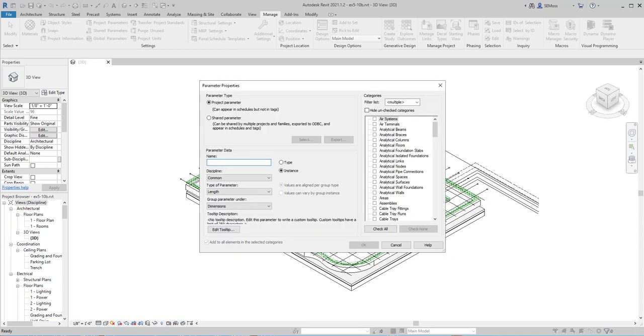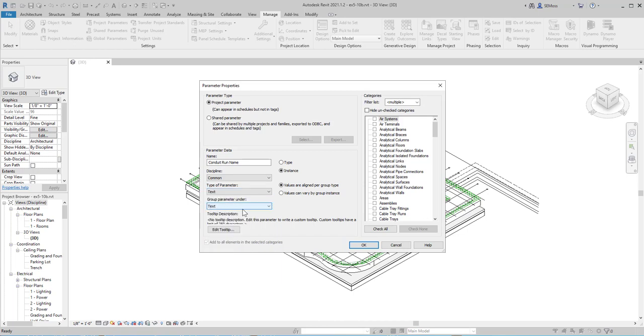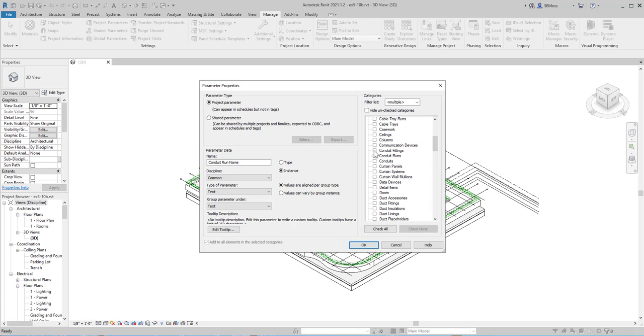We're going to click Add. We want to make sure it's a Project Parameter, not a Shared Parameter, because a Shared Parameter is an external file. We're going to call it Conduit Run Name, and it's going to be Text, and we'll group it under Text. It's going to be an instance because each conduit will have its own Conduit Run Name. We want to make sure that it applies to fittings, runs, and conduits. Then we're going to say OK.